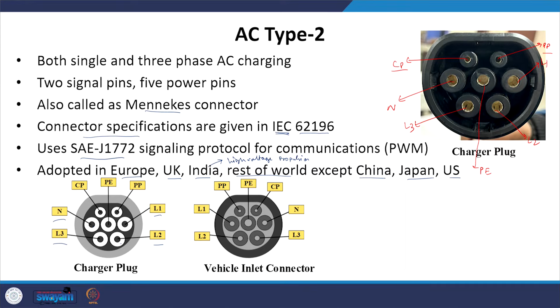If you look very carefully, this is your neutral, this is your L3, this is your L2, this is your L1, this is your protective earth pin, and this is your CP and this is your PP pin. The dimensions of the other pins like L1, L2, L3 and neutral are bigger compared to CP and PP, because over the CP and PP lines the communication takes place, while on L1, L2, L3 and neutral the power actually flows. So this is what AC type 2 is, and it supports 3 phase as compared to AC type 1, which only supports single phase.